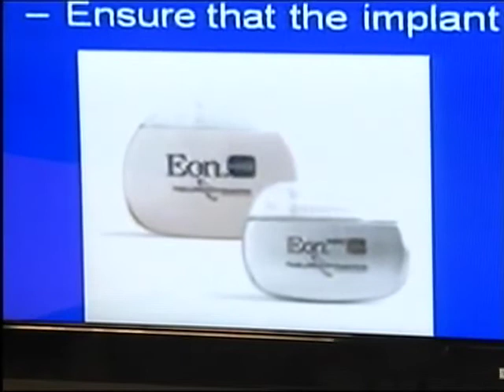Water will turn into a vapor and penetrate right through that polymer, condense on the other side, and cause damage to the electronics over a span of years. So what we use instead is a titanium hermetically sealed case. Hermetic means airtight, not watertight. So it prevents water vapor from getting in there. We use a titanium case, as we saw with these neurostimulator devices. It's the same as in a pacemaker.